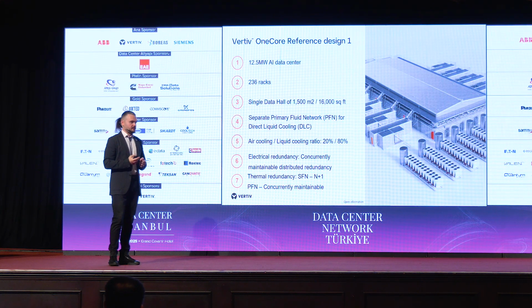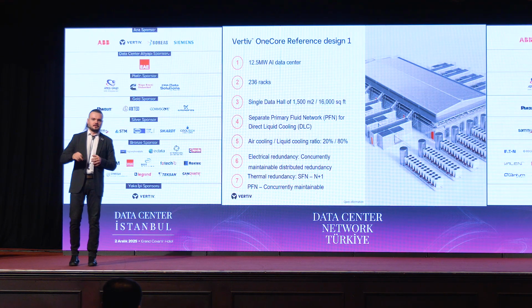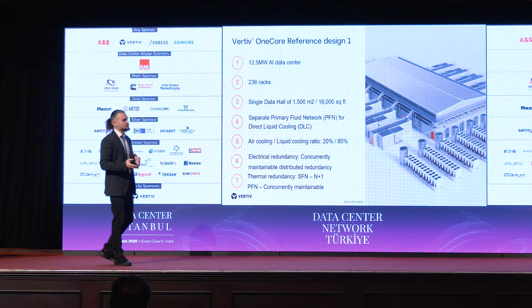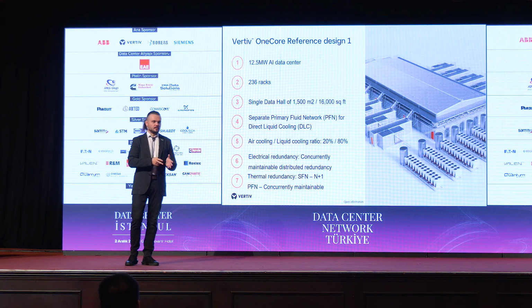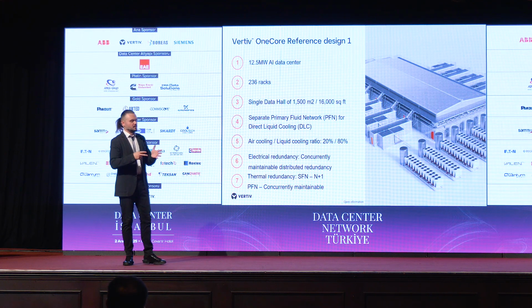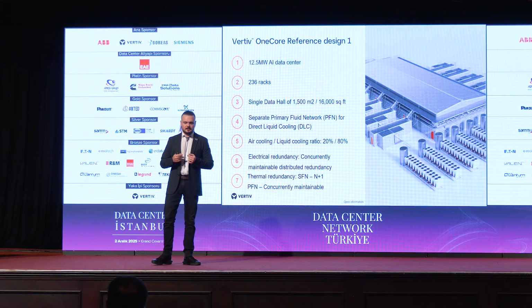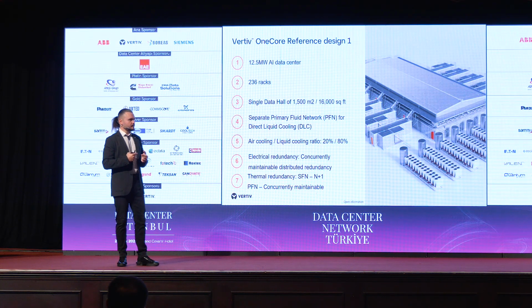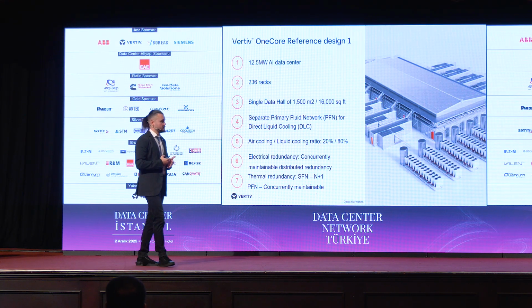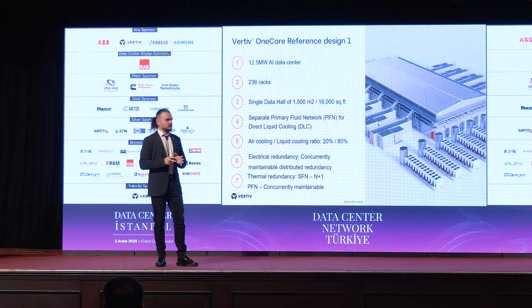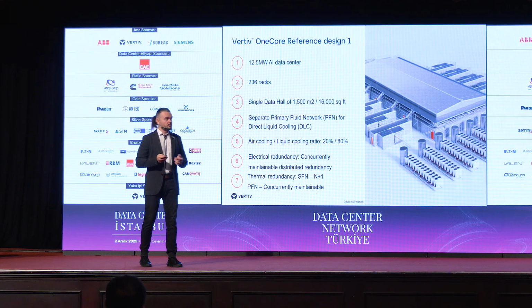Potentially, the space can be optimized, because the technology of prefabrication and working with steel allows placing components on 2 stories, even 3 stories. Potentially we can put the chillers on top of the power modules, and maybe the generators too, but it usually requires additional investment. For all the facilities we work with, if it's a greenfield, we advise starting from one level, because it's less investment, better serviceability, and the topology is basically the same.